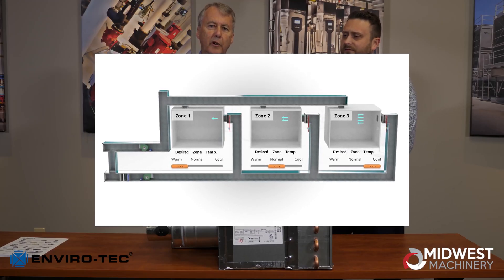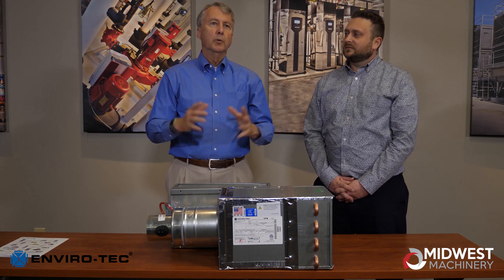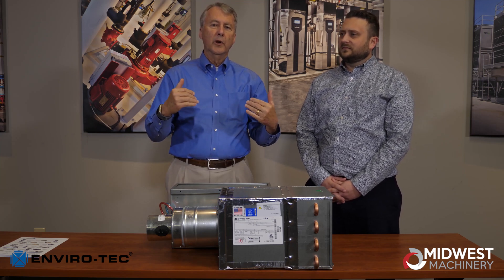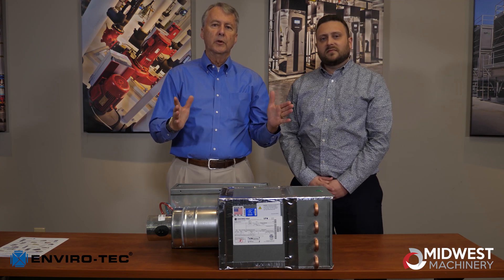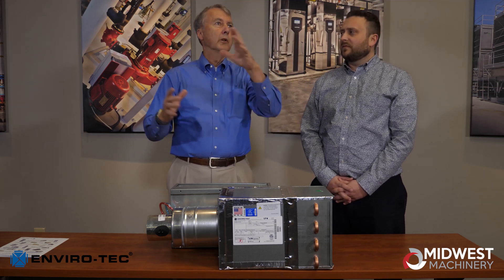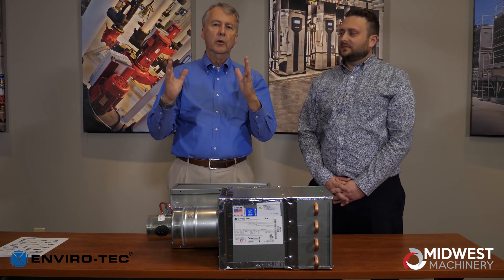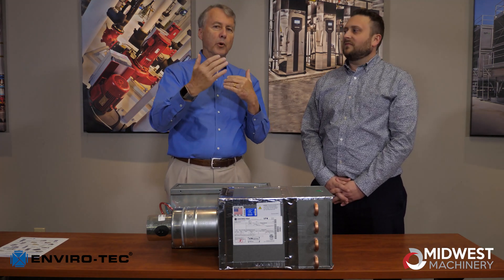We also have variable volume and constant volume products, both in the general height and low profile types, which go into larger facilities that might have chill beams around the outside. This is usually a scenario where you've got a building that is very tight and well insulated, and the chill beams along the outside take care of the immediate thermal load coming in from outside.